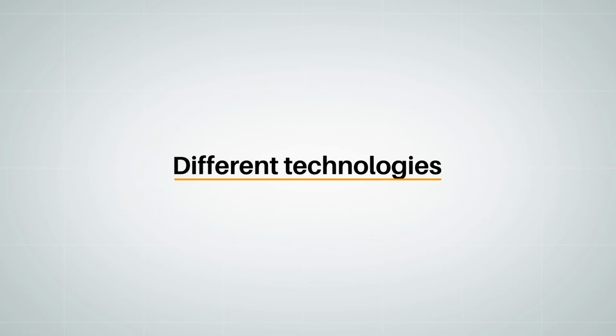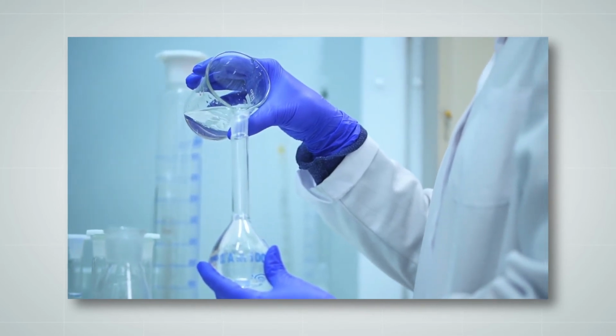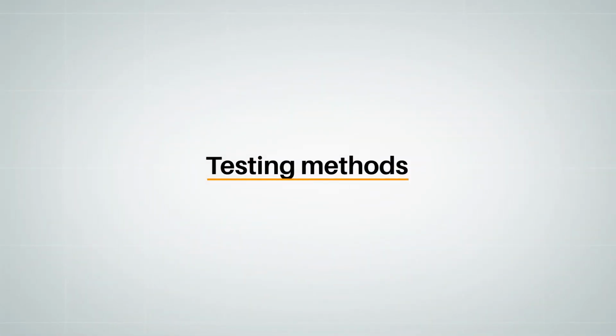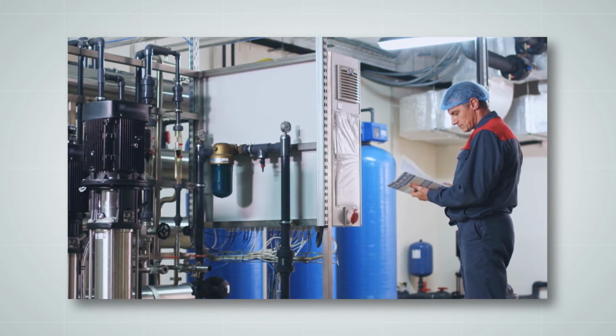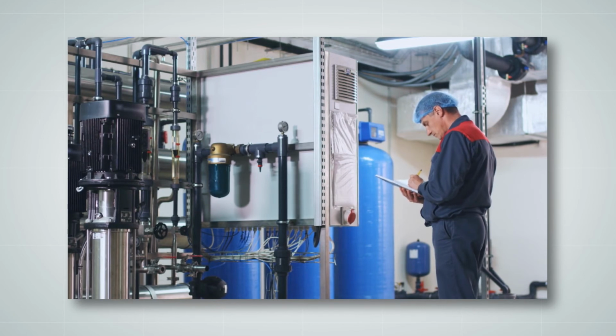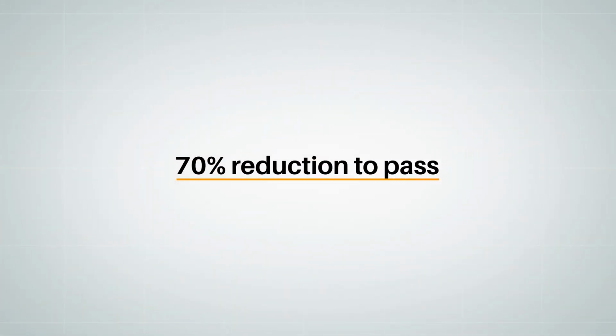The technology in a traditional water softener is based on an ion exchange that tends to reduce scaling in water pipes. The technology covered by the new standard claims to reduce or eliminate scaling without reducing the hardness of the water. Verification of performance begins with 4 test stations set up to establish where there are similar levels of scale production. Once that's done, 2 of the stations monitor performance by the devices for a minimum of 10 days, simulating flow patterns in a typical household, while the other 2 stations monitor scale production where the water is not being treated. The devices must achieve 70% reduction in scaling to pass the protocols.